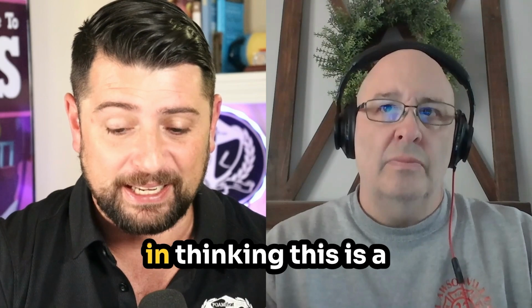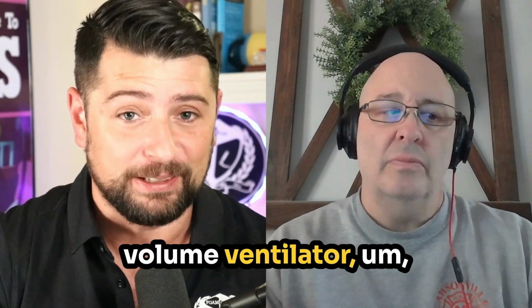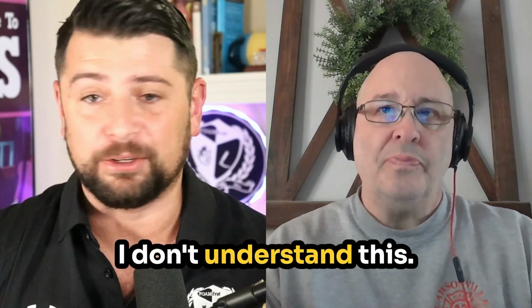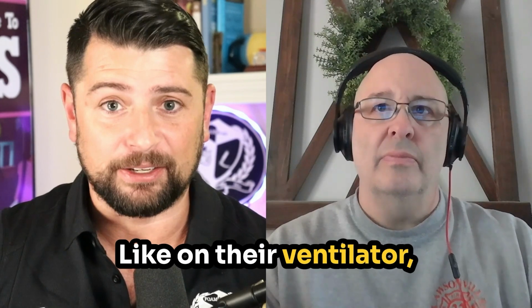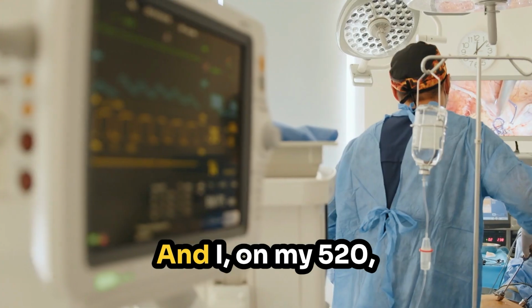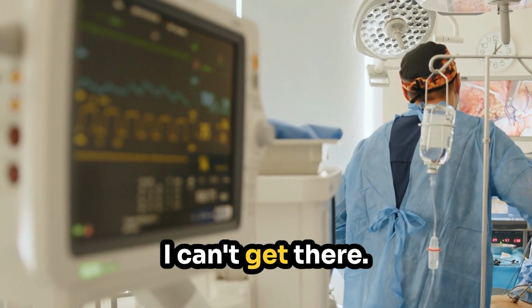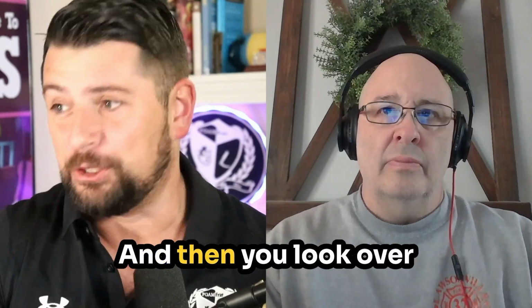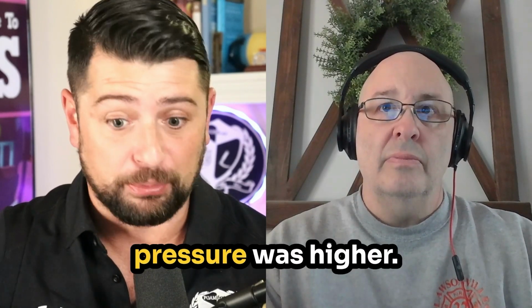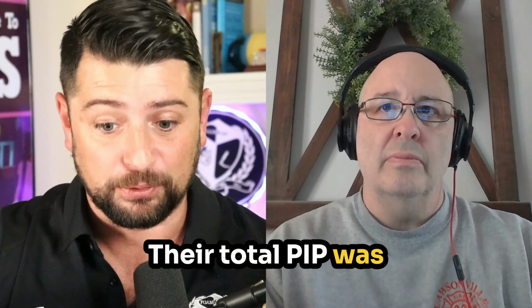And so if you're going in thinking this is a volume ventilator, you could be like, well, I don't understand this. Like on their ventilator, they're at 520 and on my 520, I can't get there. I'm only getting 300. And then you look over and you see, okay, their inspiratory pressure was higher, or their total PIP was higher on that ventilator. Anything to add to that?